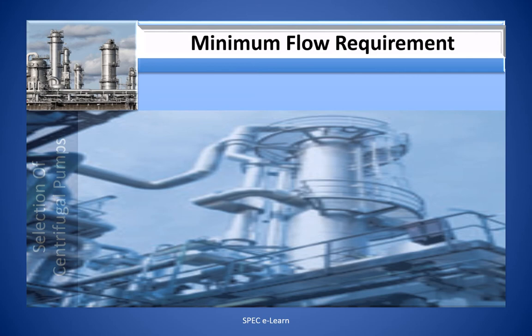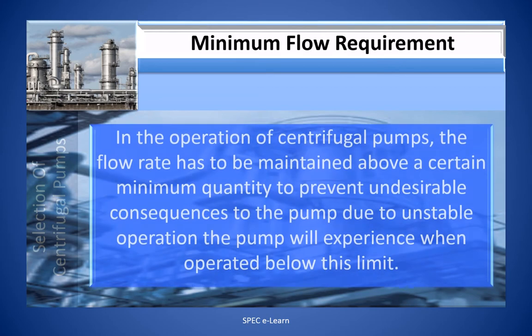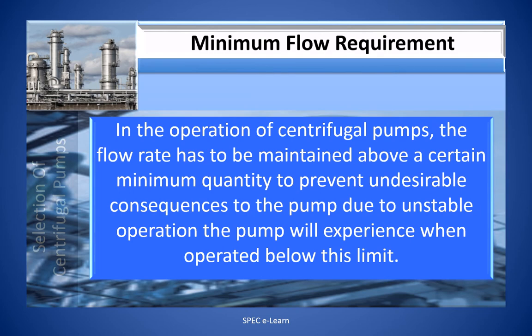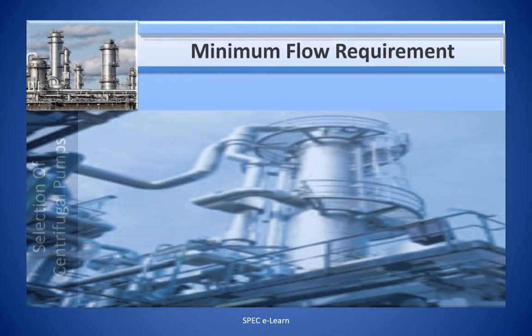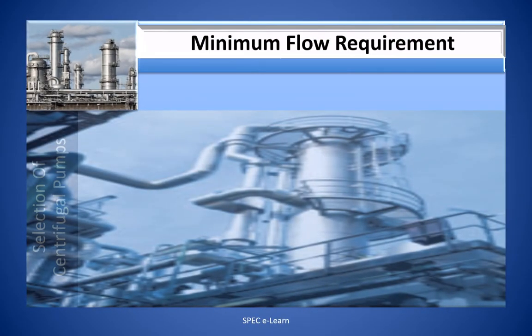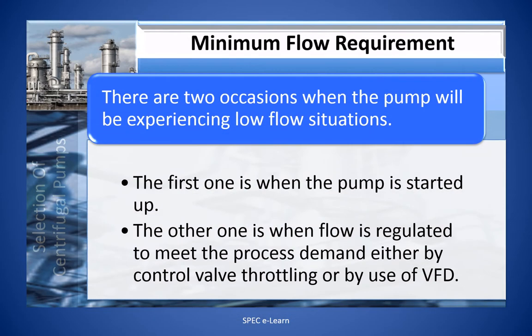When you operate a centrifugal pump, the flow rate must be maintained above a certain minimum quantity to prevent undesirable consequences due to unstable operation below this limit. There are two occasions when the pump will experience low flow situations: when the pump is started up, and when the flow is regulated to meet process demand either by control valve throttling or by use of a VFD (variable frequency drive).